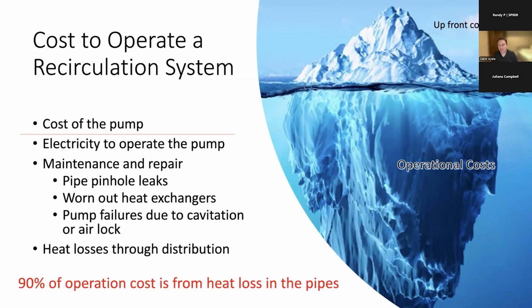It is the heat losses in the pipes. So upwards of 90% of the operational costs of a recirculation system is from the heat loss in the pipes as a result of uncontrolled recirculation. So most pumps are running either 24/7 or some suboptimal type of control that has the pump running for hours and hours unnecessarily. So really the strategy is to control the pump, and then you control those energy losses, and now it's no longer the biggest energy hog in your house.